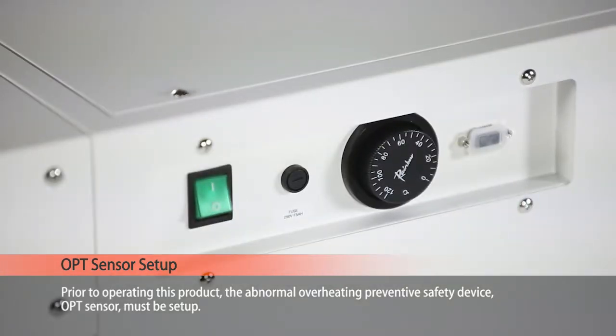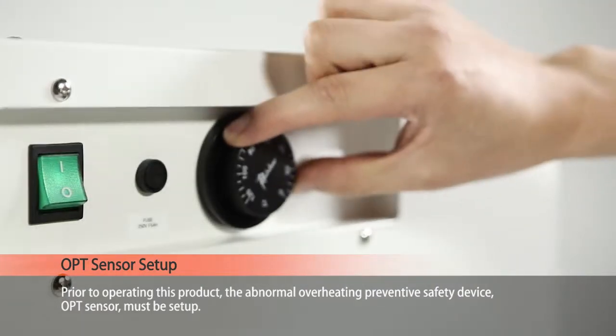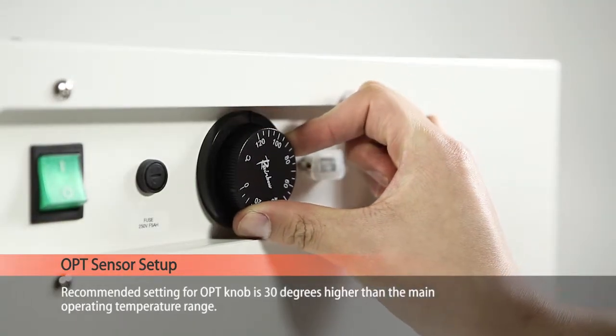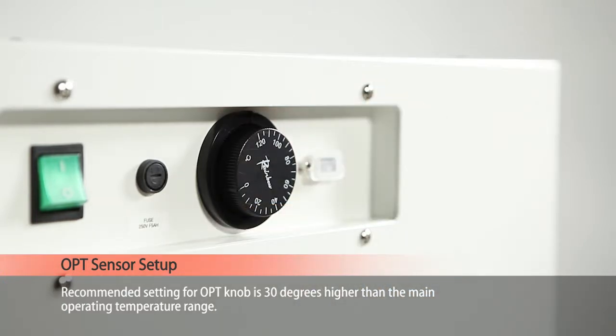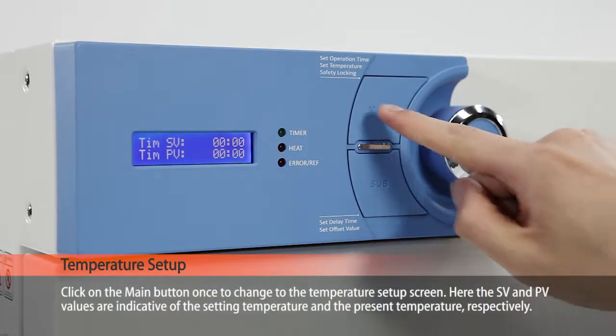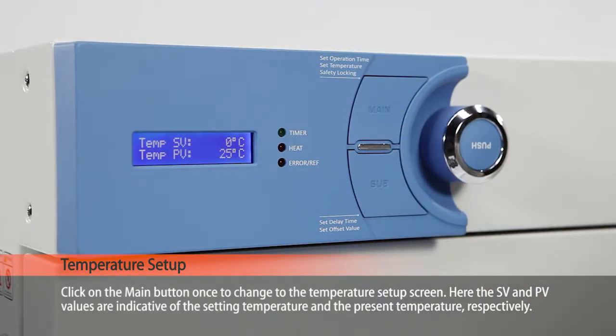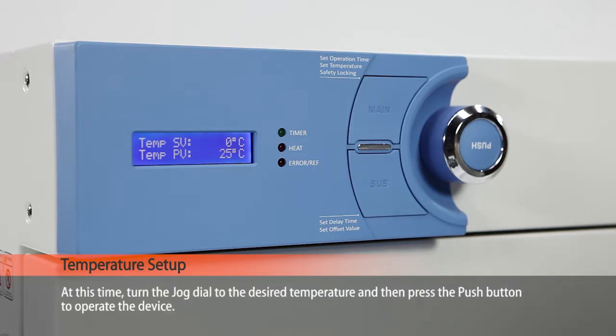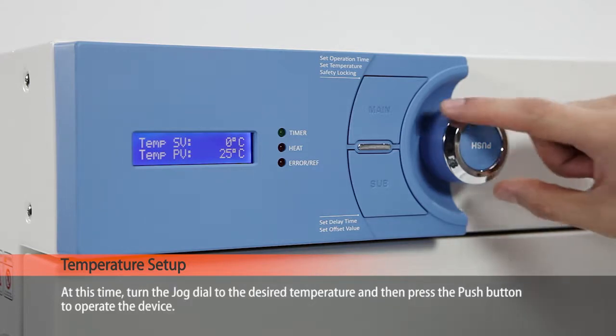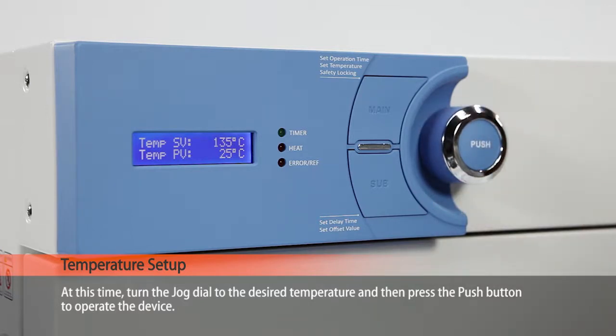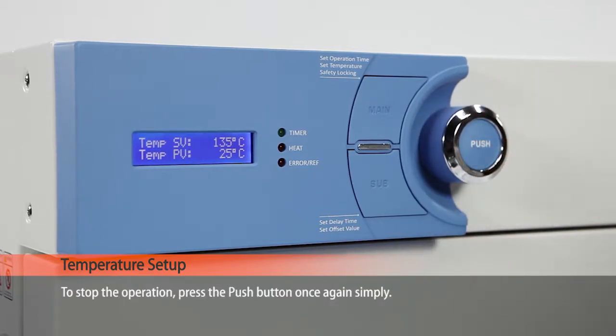Prior to operating this product, the overheating preventative safety device, OPT sensor, must be set up. Recommended setting for OPT knob is 30 degrees higher than the main operating temperature range. Click on the main button once to change the temperature setup screen. Here, the SV and PV values are indicative of the setting temperature and the present temperature, respectively. At this time, turn the jog dial to the desired temperature and then press the button to operate the device. To stop the operation, press the push button once again simply.